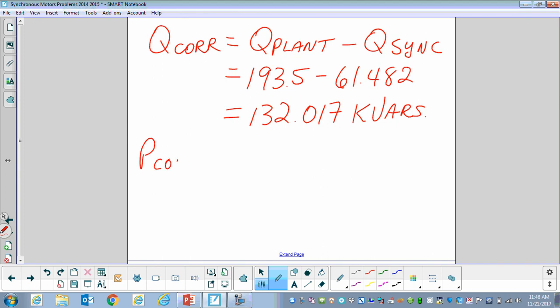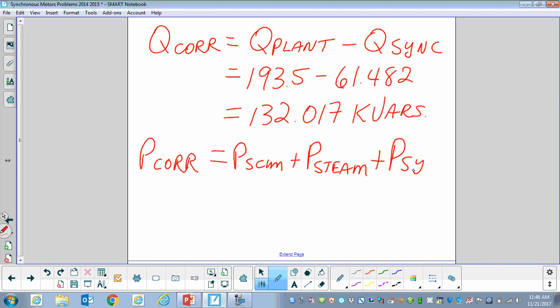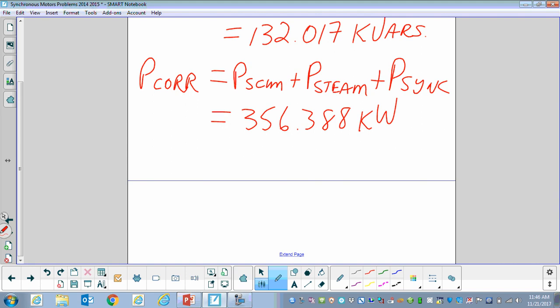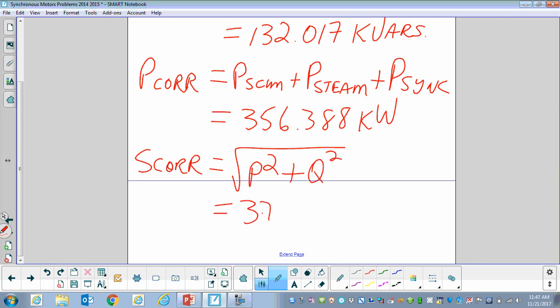Power corrected: because we had the synchronous motor, we know we had some resistance there. So we add P of the squirrel cage induction motor plus P of the steam plus P sync. Adding all three together, we come out to 356.388 kilowatts. Then we can figure out S corrected using the Pythagorean theorem: P squared plus Q squared, using all the corrected numbers. Done correctly, we come out to 379.97 kVA.